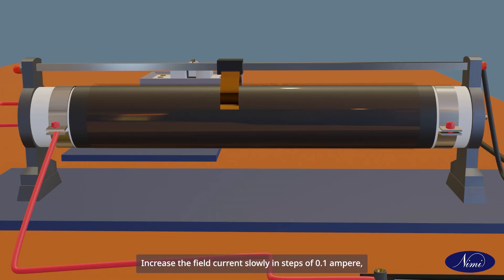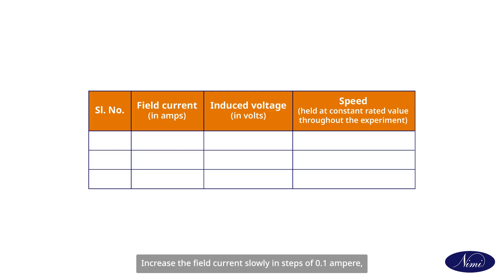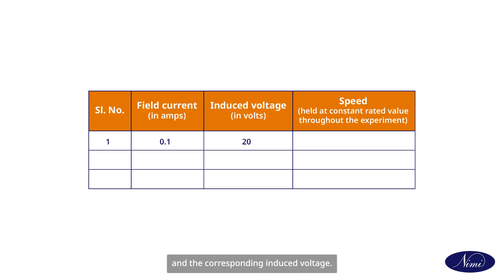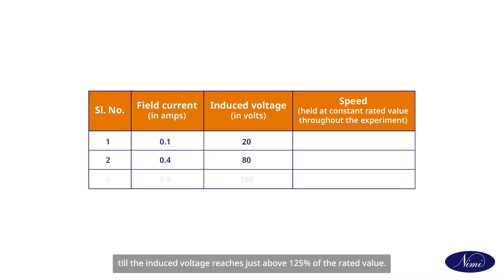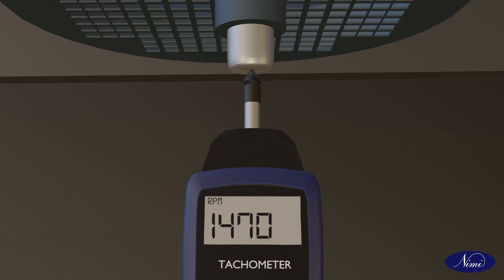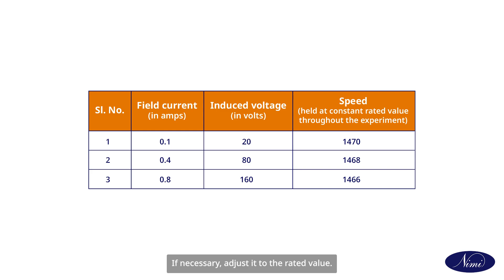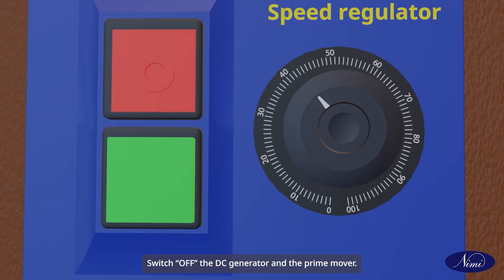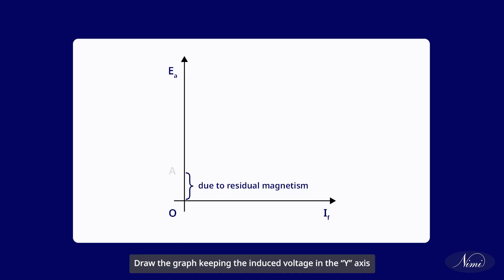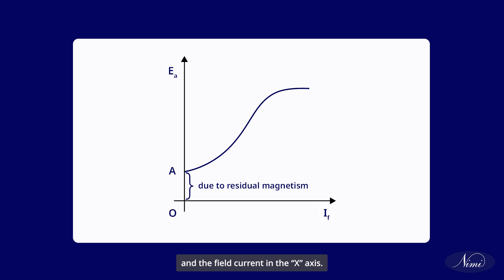Increase the field current slowly in steps of 0.1 ampere, and for each step note down the field current and the corresponding induced voltage. Increase the field current only till the induced voltage reaches just above 125 percent of the rated value. Check the speed of the generator at intervals and, if necessary, adjust it to the rated value. Switch off the DC generator and the prime mover. Draw the graph keeping the induced voltage on the Y-axis and the field current on the X-axis.